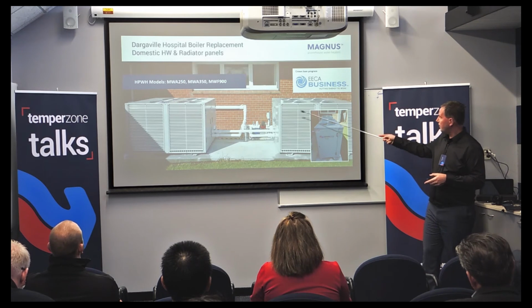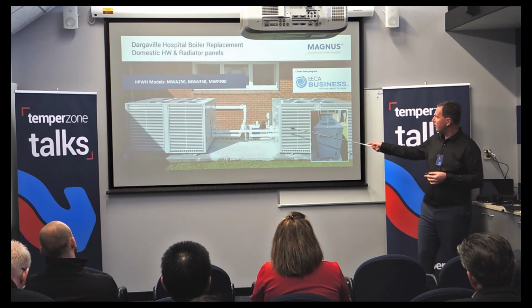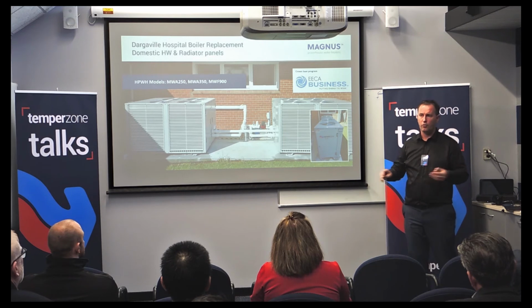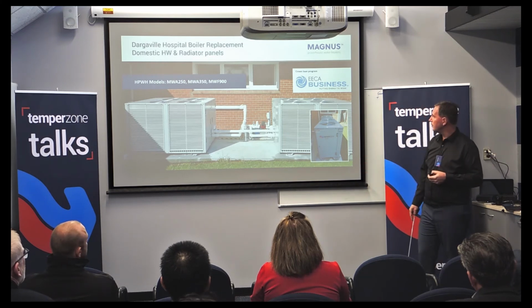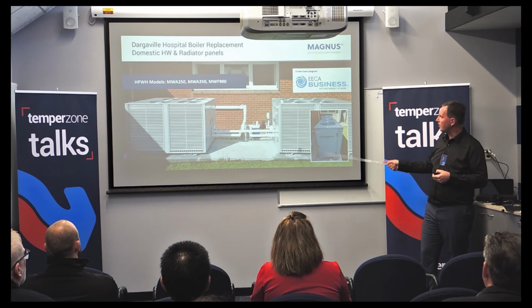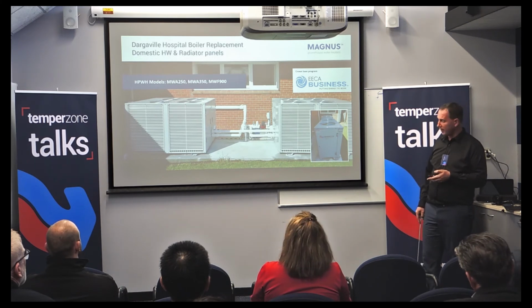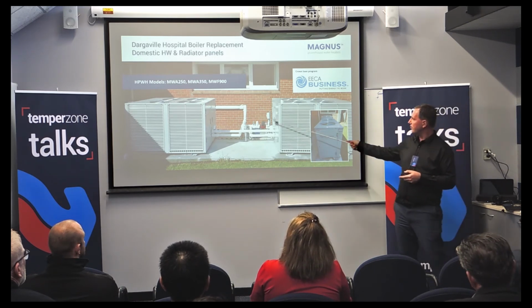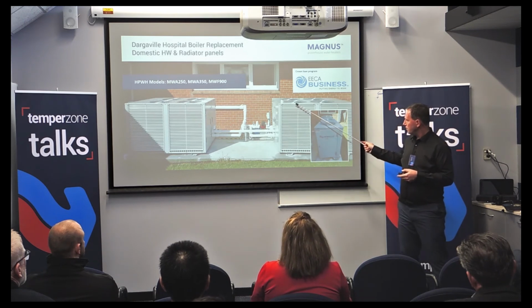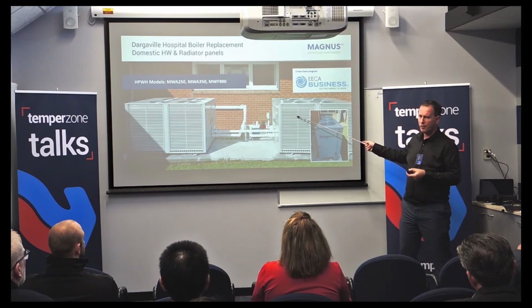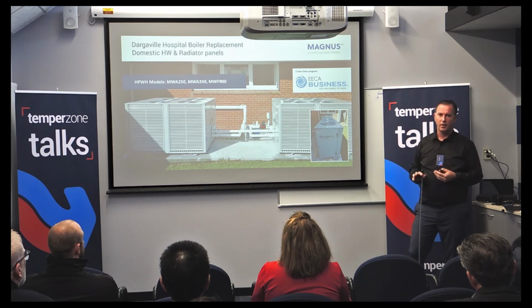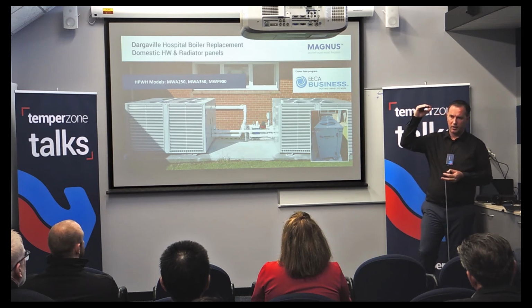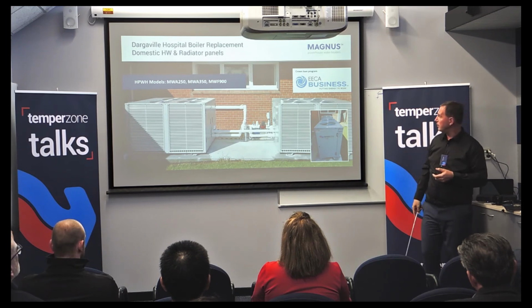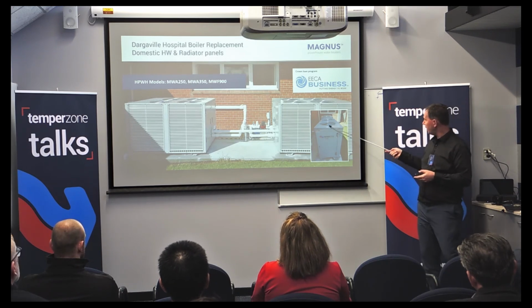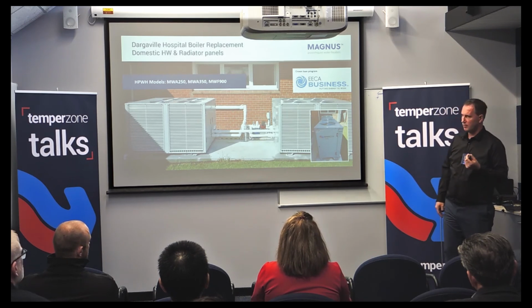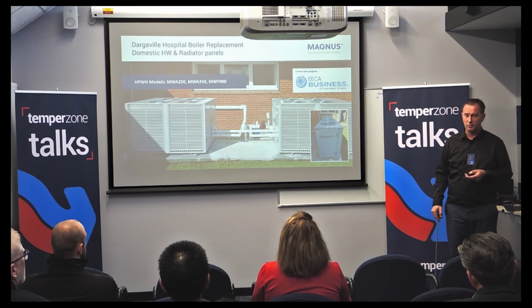And we basically have set up a bunch of these units. So these 2 units here do all the wards of the hospital. It's 180 kilowatts installed capacity. It's an inline system. There's no buffer tanks. The 55-degree water out of these inverter-based units goes directly to a series of radiators and ceiling panels around the wards. These are the domestic hot water systems.